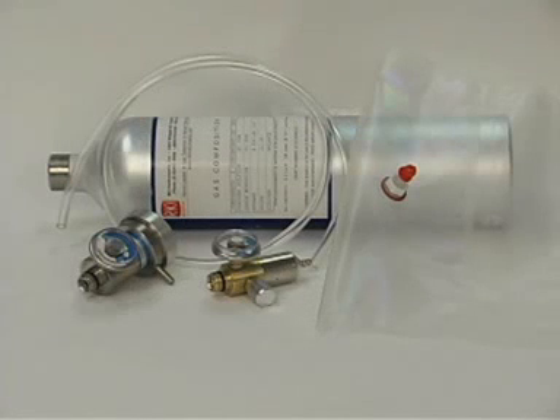You will also need tubing, a demand flow regulator or a dispensing valve and gas bag to provide adequate sample gas flow. Utilizing the demand flow regulator and RKI 4-in-1 cylinder is the most efficient procedure and is the equipment used in this training.